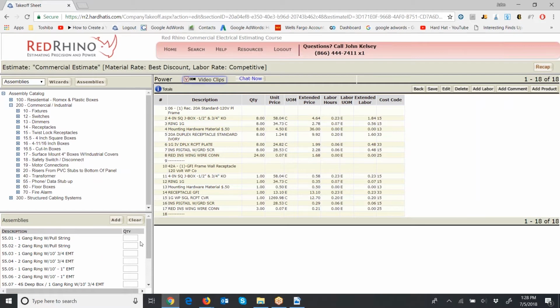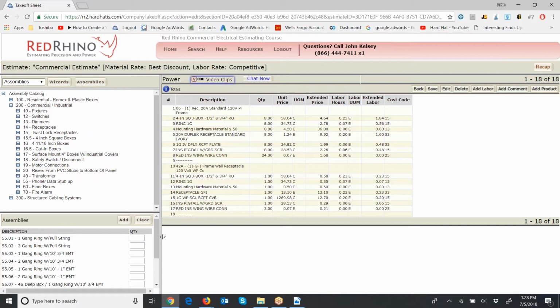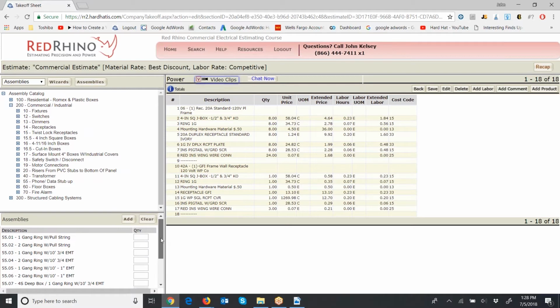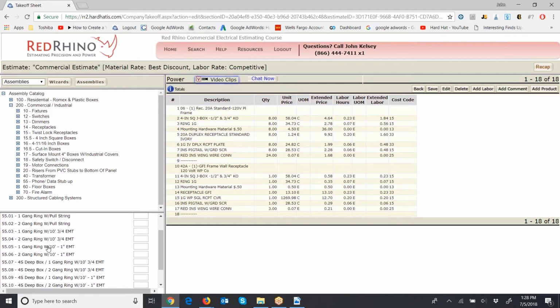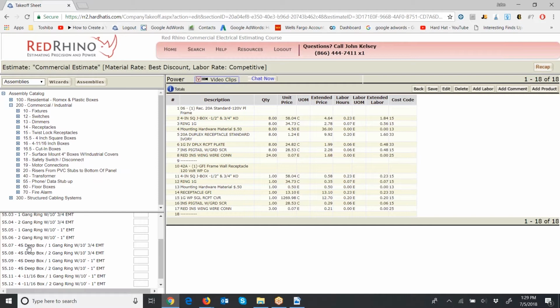Now, in this case, I'm looking for one with a 4S box, a ring, and 10 foot of 3/4. So here's a 1-gang ring with 10 foot of 1 inch, right above that is a 2-gang ring. Again, these are still in the rings, I'm looking for a 4S box. So here's one, 4S deep box, 1-gang ring with 10 feet of 3/4 inch EMT. I'm going to use that one.